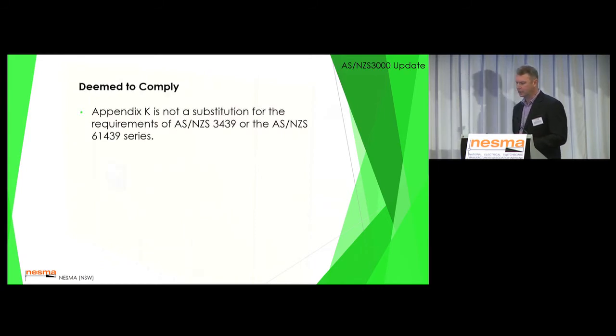So firstly, deemed to comply. Basically what this means is that Section K is not a substitution for 61439 or 3439. We're talking about introducing some of the clauses into AS 3000 that make it easier to reference back to 61439 for understanding. So if you comply with 61439, you're deemed to comply with these clauses in AS 3000.